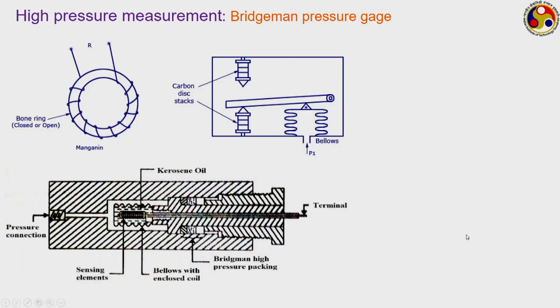Elastic pressure transducers can have quite a good range, like using Bourdon tube gauges we can go to quite high pressure values, but they are also more suitable for moderate to relatively high pressure measurements, whereas the diaphragm kind of gauges are more used for low pressure measurement or small pressure difference measurement. Electric pressure transducers again can have good ranges for low to relatively high pressure measurement. But now we are going to talk about another one, which is again an electric pressure transducer, but that is specifically used for measuring high pressure. High means it is really high pressure that we are going to talk about, which is the Bridgman pressure gauge.